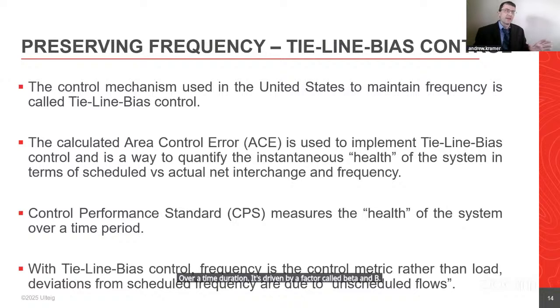We're not going to go into that measurement here, but it is something that is available for you if you ever want to look this up online. And I'll mention the control standards here in a minute in case you ever want to do a little bit of research yourself. With tie line bias control, the key thing is the frequency is the control metric, not the load itself. If you're in Europe or certain segments of it, the load is actually the control measure rather than the frequency. In the United States, you have, let's say, a generator tripping offline, the frequency drops, and the load subsequently responds. That is what actually happens.